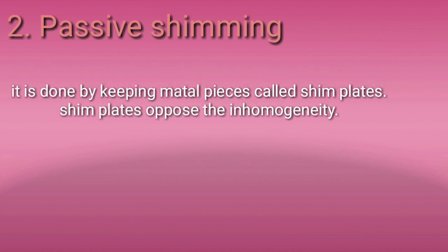In passive shimming, metal plates are placed near the magnetic field. These are called shim plates, which oppose the inhomogeneity. This is how passive shimming works, and through this, magnetic field homogeneity is maintained.